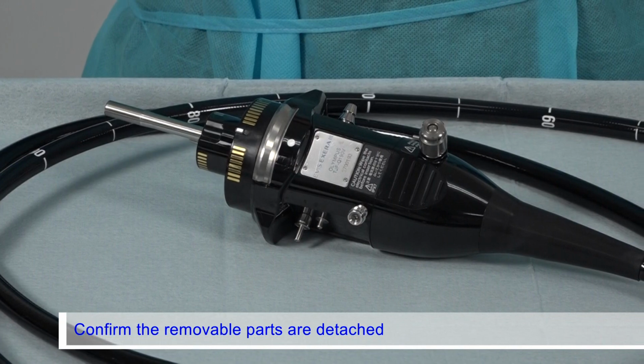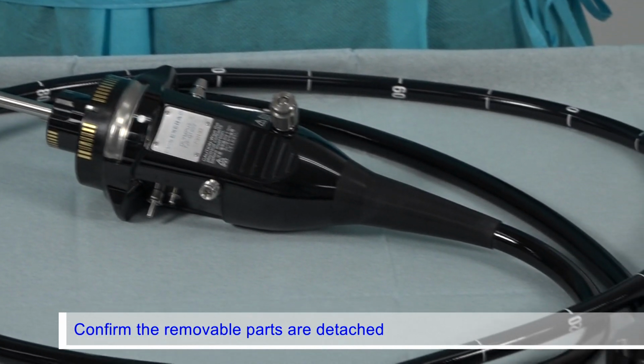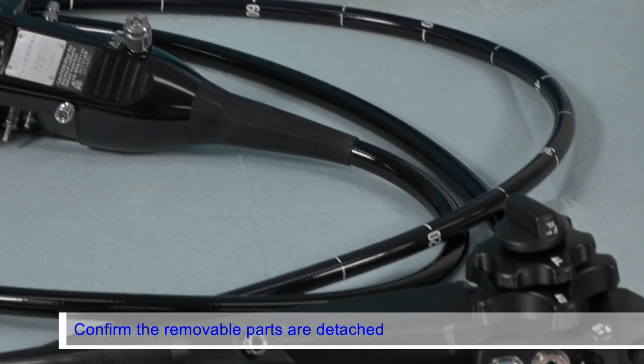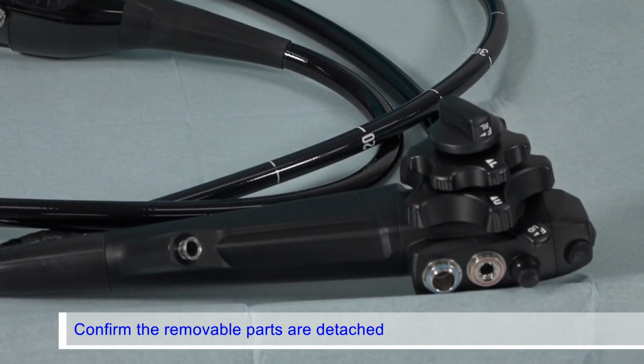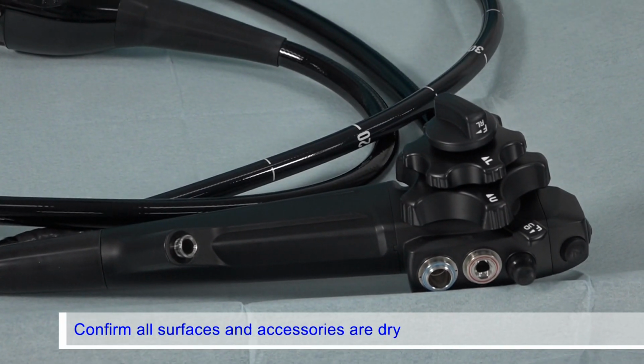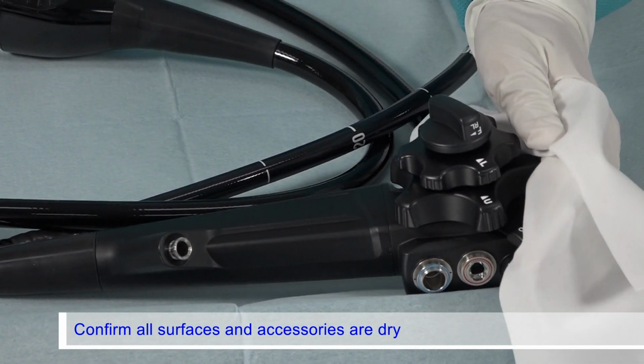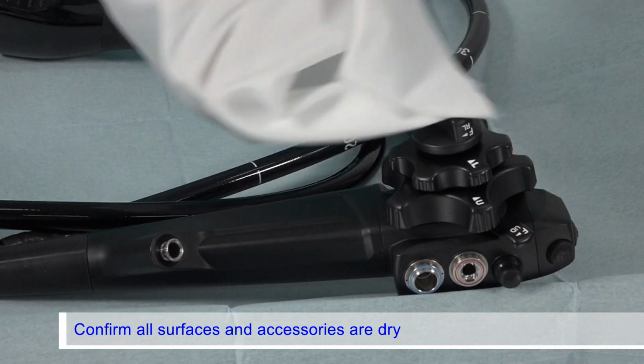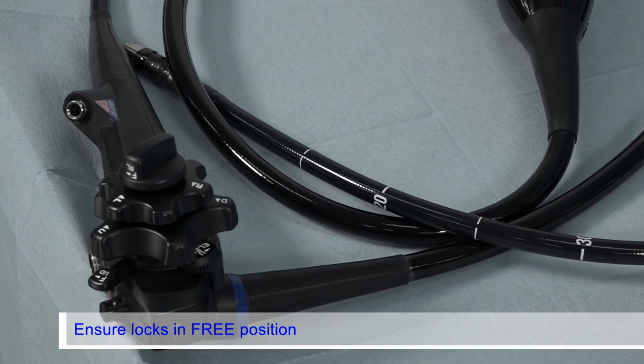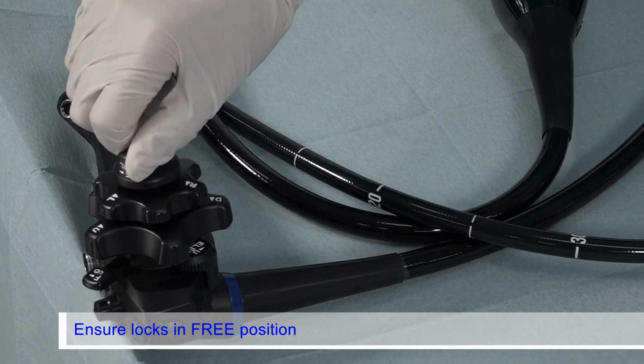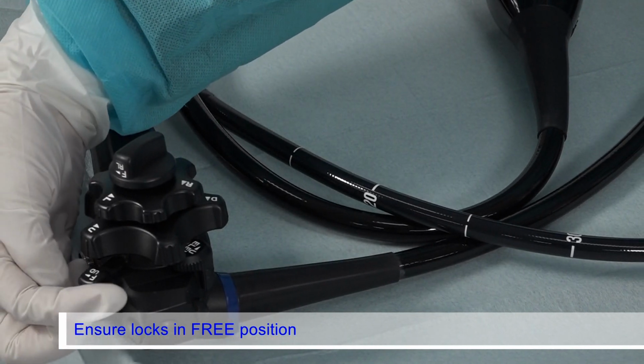Confirm that all accessories, namely the air-water valve, the suction valve, and the biopsy valve, are detached from the endoscope. Confirm that all surfaces of the endoscope and accessories are dry. Place the endoscope's angulation locks in the F position.